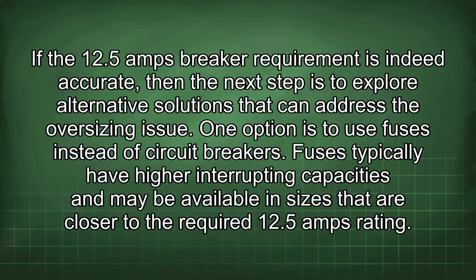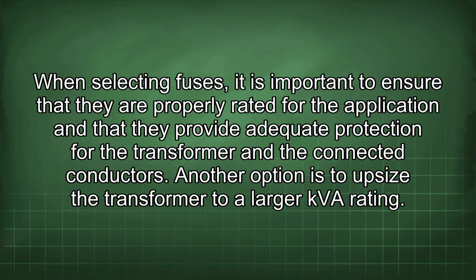If the 12.5 amps breaker requirement is indeed accurate, then the next step is to explore alternative solutions that can address the oversizing issue. One option is to use fuses instead of circuit breakers. Fuses typically have higher interrupting capacities and may be available in sizes that are closer to the required 12.5 amps rating. When selecting fuses, it is important to ensure that they are properly rated for the application and that they provide adequate protection for the transformer and the connected conductors.